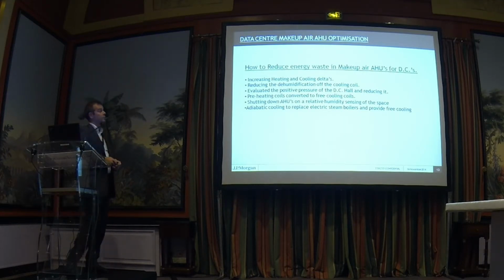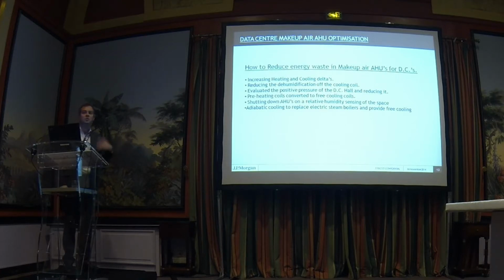Shutting down the AHUs on relative humidity sensing of the space. So if your humidity in your data center is at 50%, or 60%, or 45%, just turn them off, or spin them right down so you get air going in there just to keep the dust out. But just turn off humidification, and only run it when your humidity starts to drop. A lot of people try to run their data centers like art museums. They try to maintain 50% humidity.